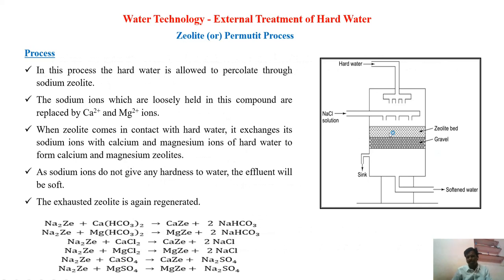The process uses a zeolite bed made up of sodium aluminosilicates — represented simply as Na₂Z. Hard water is allowed to pass through this zeolite bed. As it passes, the sodium ions on the surface of the zeolite are exchanged with the calcium or magnesium ions present in the hard water. All spots in the zeolite bed gradually become occupied by calcium and magnesium ions, replacing all the sodium ions.